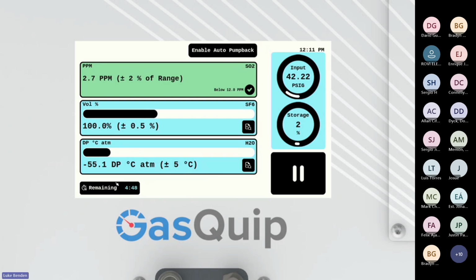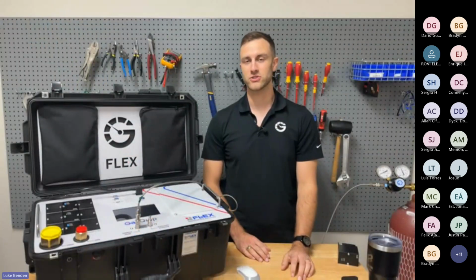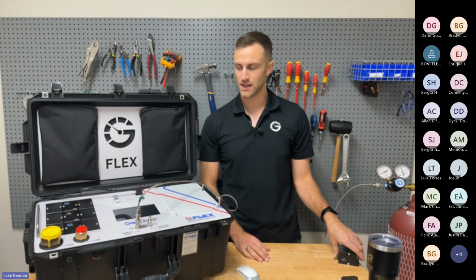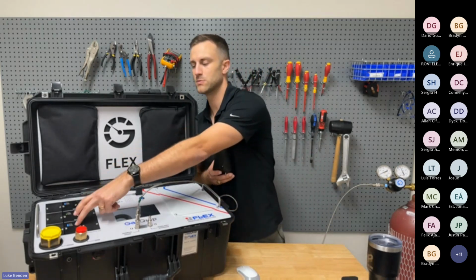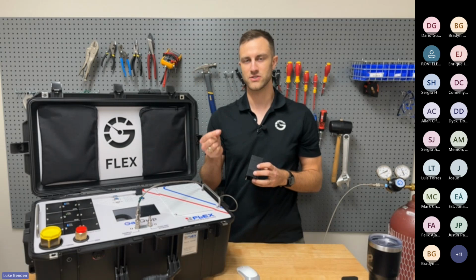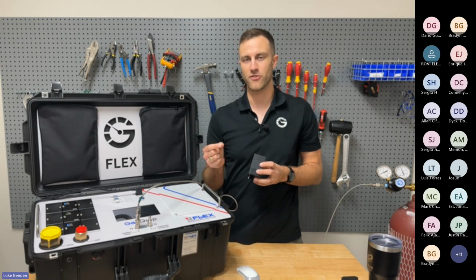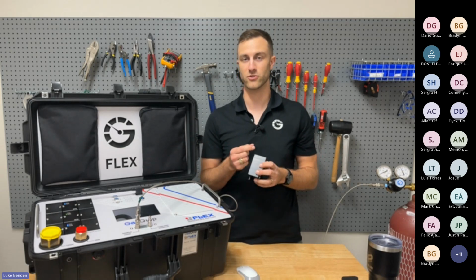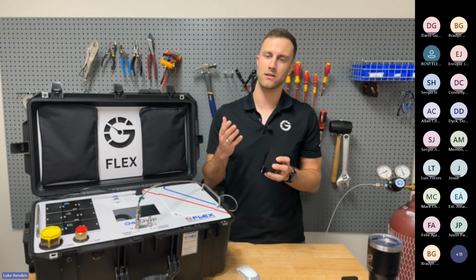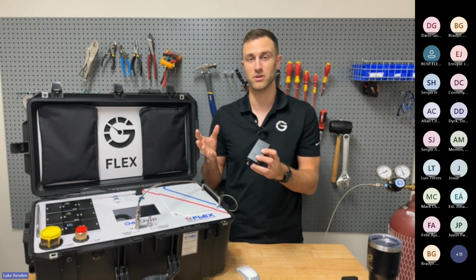So the first test of the day will run for about 12 minutes, and then subsequent tests will run for about 7. I've already run a test for today, so this test is only going to run about 7 minutes in total. The reason that the first test runs a little bit longer is that our H2O sensor has a built-in heater at the tip of the sensor, and that heater helps to burn off residual moisture left over from storing the analyzer and just general moisture that tends to build up inside the device.